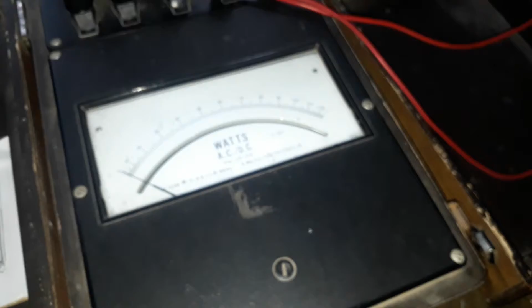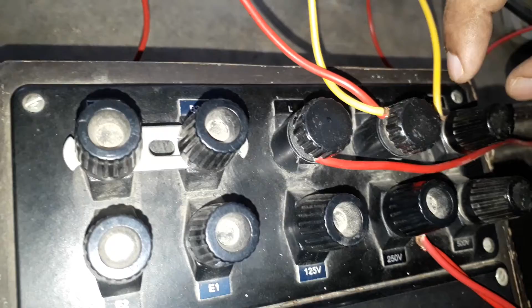So from the wattmeter we have to bring our supply to the ammeter and onwards. First of all, let us see how to make the connection for the wattmeter. Invariably, whenever we use a wattmeter, there are various terminals. As you can see over here, there is L, M, C or COM, then there are voltage ranges. To begin with, we will always short circuit the M and COM, common terminals. And then from L, we will take the connections forward.